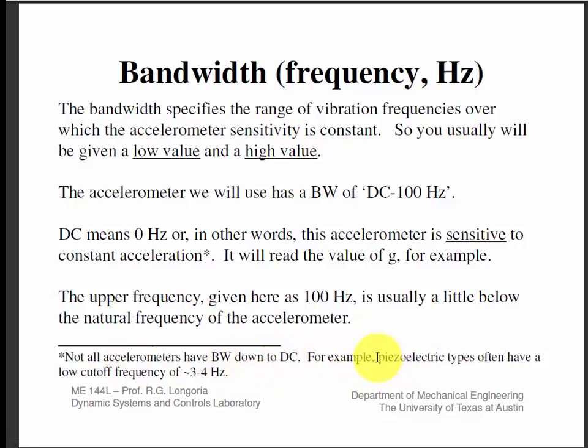Not all accelerometers have a bandwidth that goes down to DC. As I mentioned, piezoelectric types will not read DC. They roll off on the low frequency, so you can't read a constant value. If you turned the sensitive axis of a piezoelectric accelerometer to be sensitive to Earth's gravitational field, it would basically read zero because it can't read a constant. But if you start shaking it at a certain frequency above four or five hertz, it'll read that.